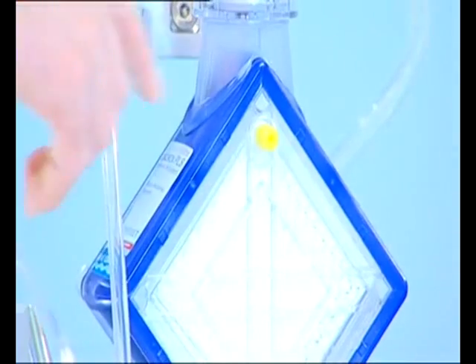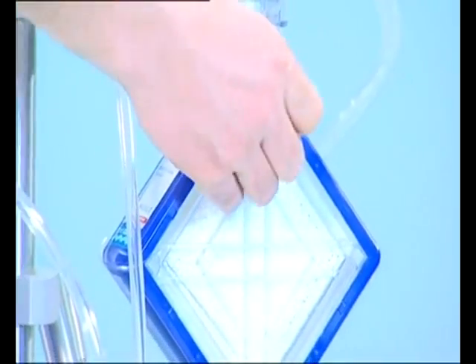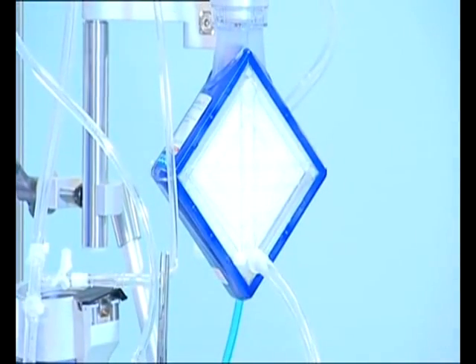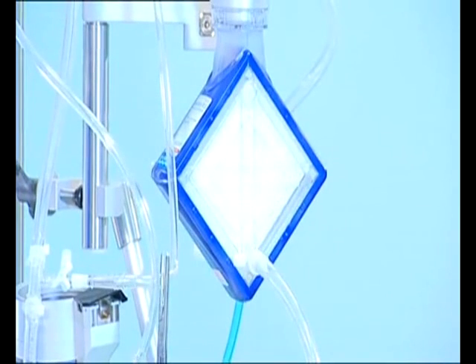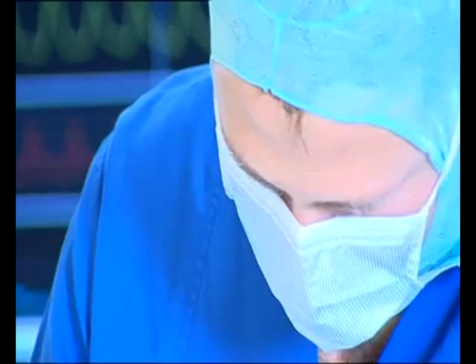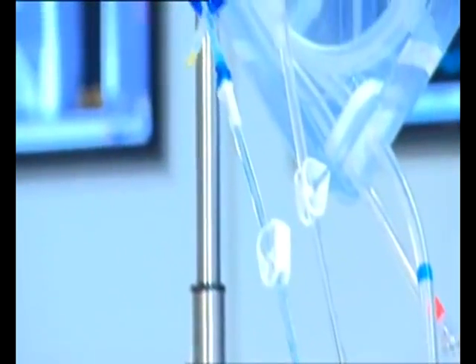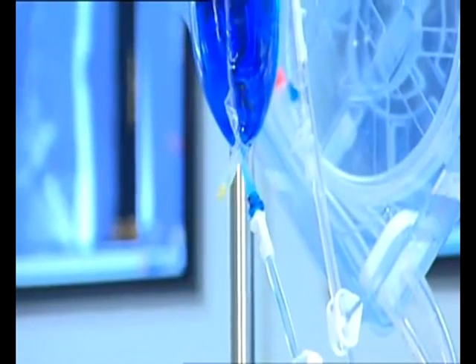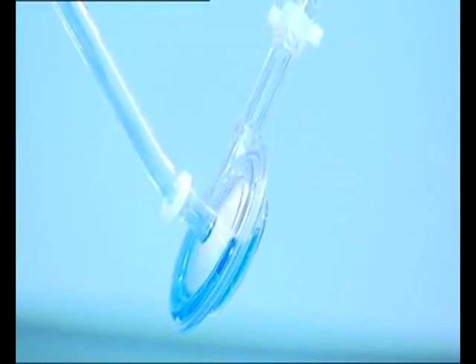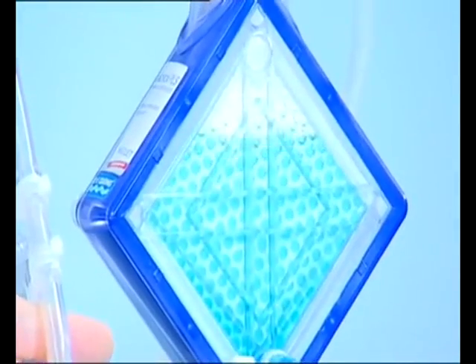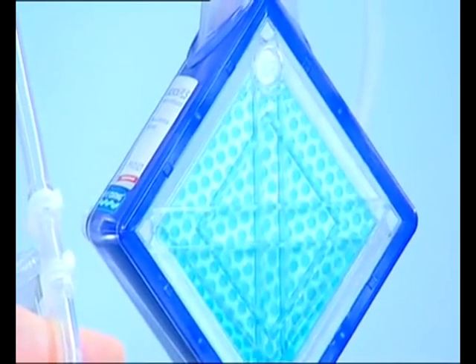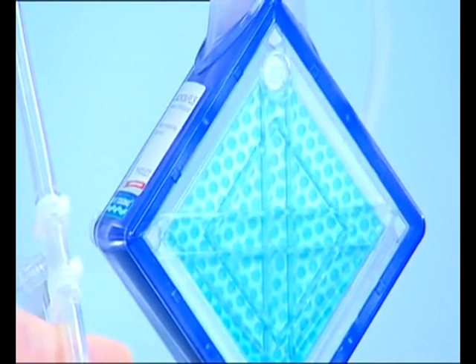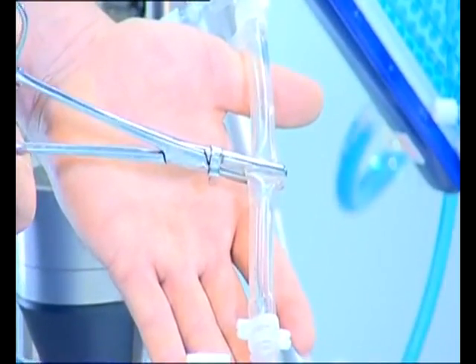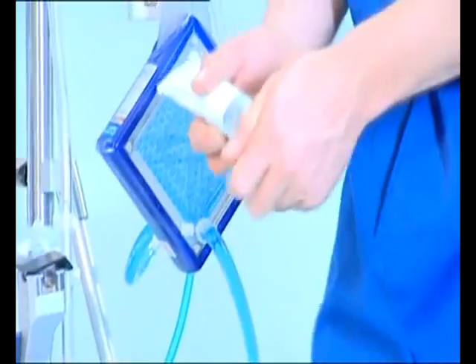The yellow luer cap on the venous side of the oxygenator is removed. Behind this cap is an automatic de-airing membrane. This membrane allows air to pass through and out, but is leak-proof for fluids. When the priming line is opened, solution flows by gravity into the centrifugal pump and oxygenator. By tilting the centrifugal pump slightly, any contained air will pass into the oxygenator and escape automatically through the de-airing membrane. An air bubble below the clamp will escape when the clamp is open for a short moment.